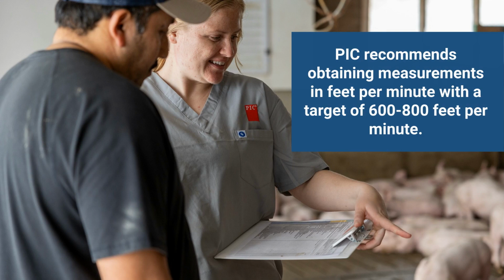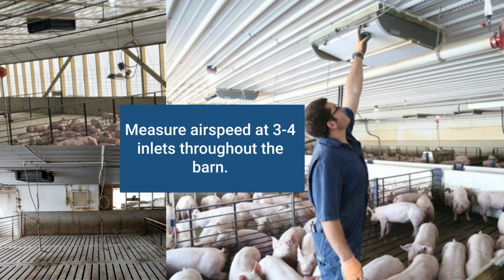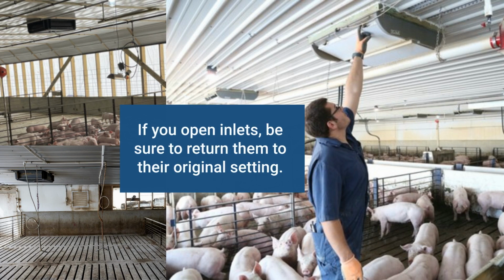PIC recommends obtaining measurements in feet per minute with a target of 600 to 800 feet per minute for most barns. It is recommended to measure airspeed at 3 to 4 inlets throughout the barn. If you manually opened inlets further, be sure to return them to their original setting.